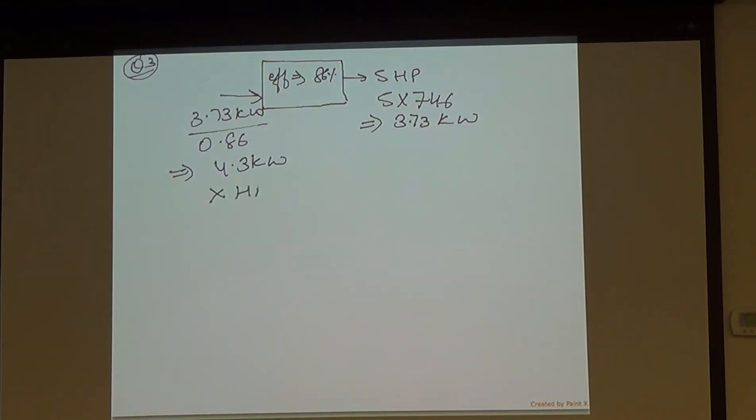How many hours am I running this machine? 150. So energy consumed will be in kilowatt hours, which is? 650. 650 kilowatt hours? Yeah. Guys, make sure you check our math. I just want to verify, 4.3 times 150 equals 645. Yeah, that's fine. We are just calculating kilowatt hours before we calculate the dollar value. So it's like 650 candies is what you have to buy. One candy is 10 cents. You will be paying 65 dollars. That's what we are going to do. One kilowatt hour is how many cents? Ten cents.